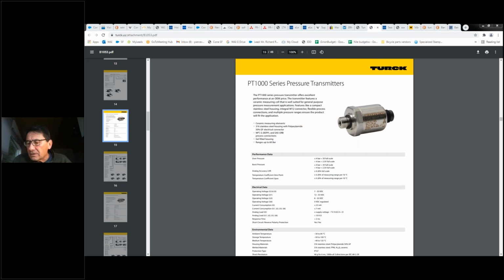So we have a best practices presentation that is part of this class series that shows you how to install those shielded cables properly using the tool to strip 1 inch off of the outer jacket, typically midstream on the cable, clamping it to a ground clamp, and then running the shield right up to the termination points on whatever device you're using to read the signal from the pressure sensor. Drop me a line and I can send that to you.